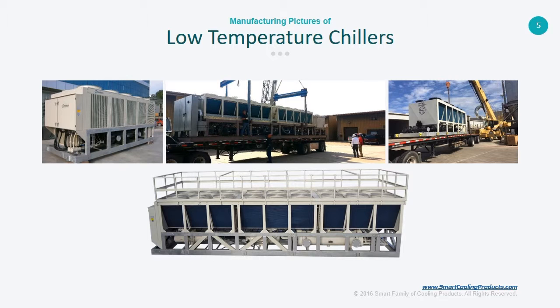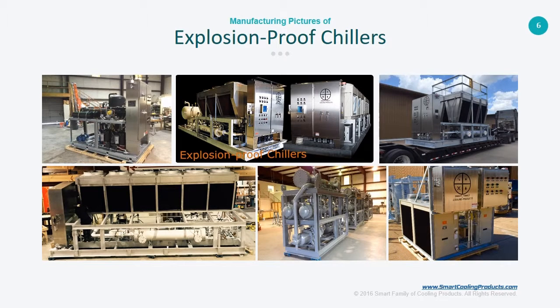Moving on to the explosion-proof chillers. The unit on the bottom left there is an SSCD 150 screw chiller designed for an MRU application, a mechanical refrigeration unit application. The top left there is a chiller with R404 refrigerant. It was cooling 33% methanol, explosion-proof as well. And the unit in the top right is an SSCD 80, Class 1 Div 2 Group B air-cooled screw chiller with a condenser handrail system, as you can see there around the top of it. That unit was cooling propylene oxide.